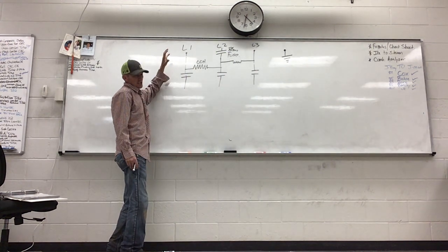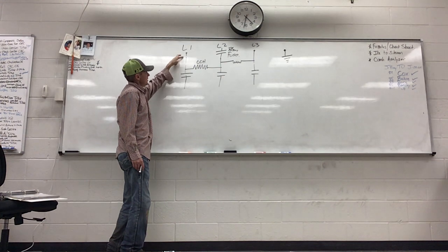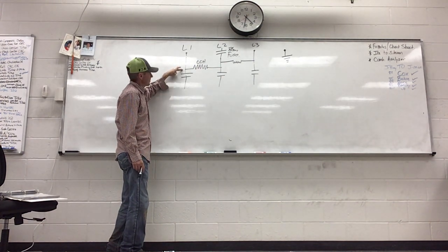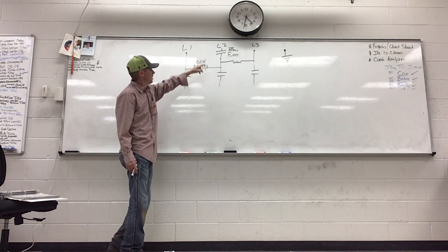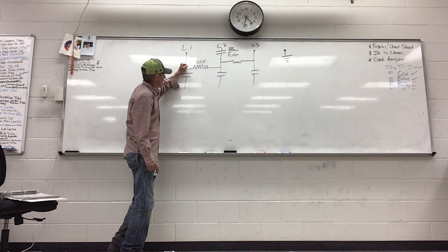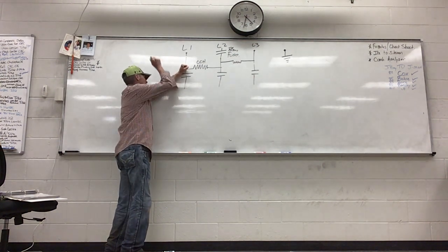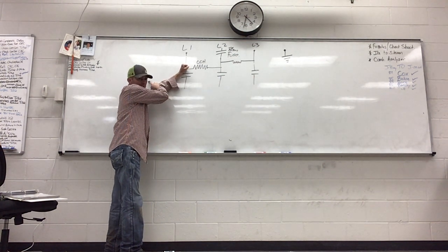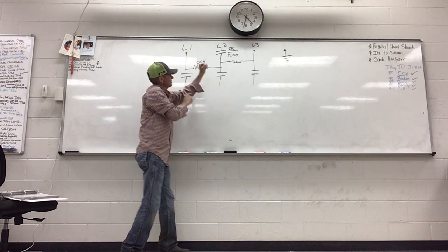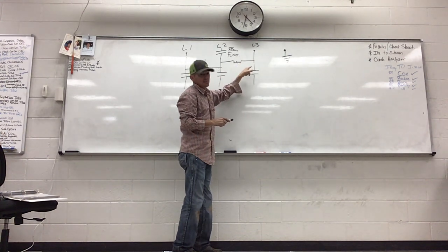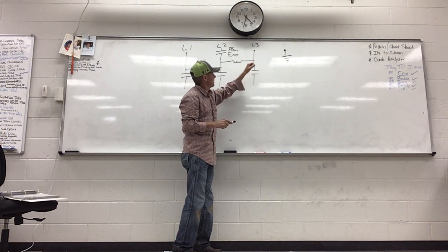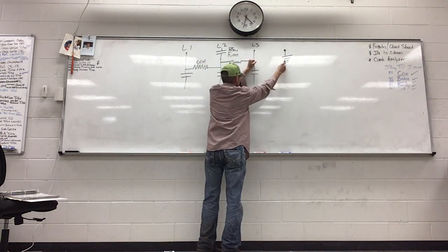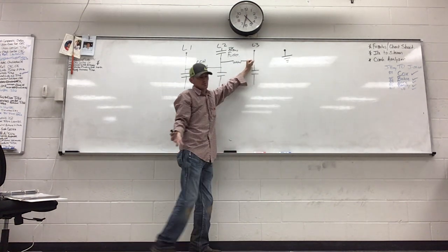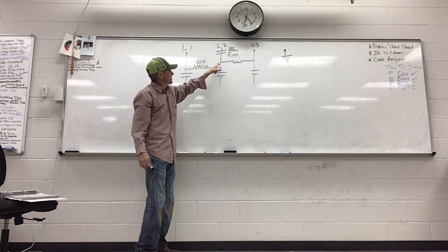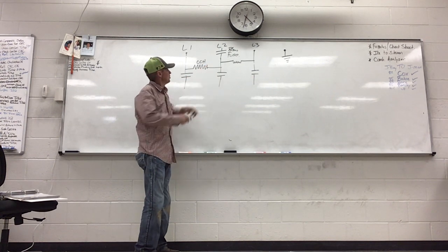So, let's talk about checking each line to ground. L1 is hot. The only thing we've lost is L2. If I check L1 and compare it to ground, if I've got a good ground on a 208 building, I'm going to get 120 volts, right? L3 is hot. I'll skip L2 on purpose. If I check L3 and compare it to ground, I'll get 120 volts on a 208 building. But then we know L2 is dead.